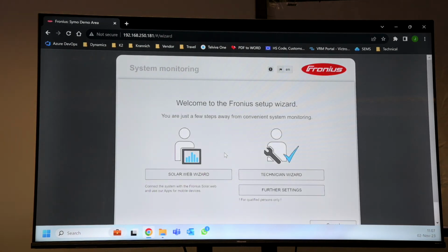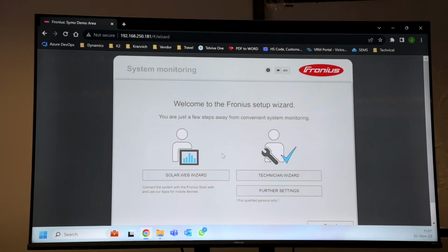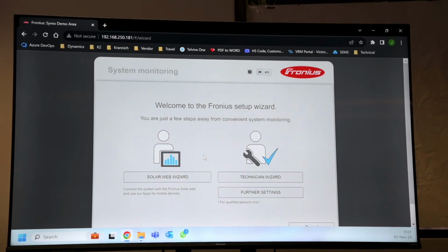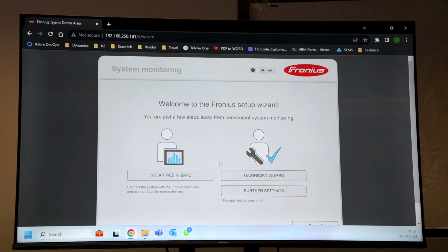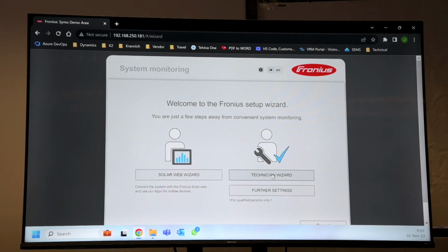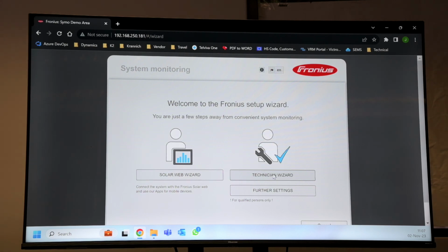So next is telling you that the app is available on Android and iOS if you want to download it for SolarWeb. So first we'll start with the Technician Wizard. Again, make sure that your DC isolator is in the off position, because if it is on, the unit will start producing power. So if you have not told the system that there's a smart meter or feeding limitation on the site, you can end up pushing against the grid itself. Smart meters at the moment do trip the minute you are pushing back against the grid. So just make sure that the DC isolator is off.